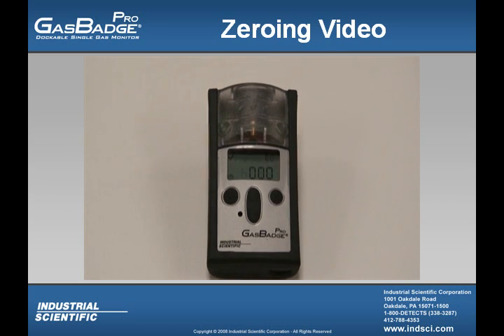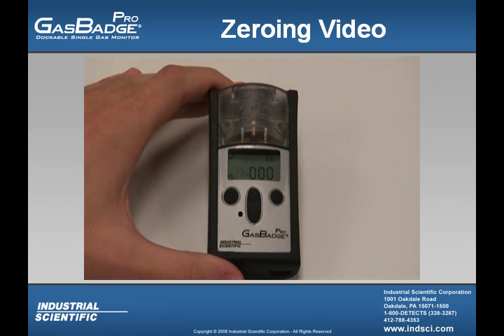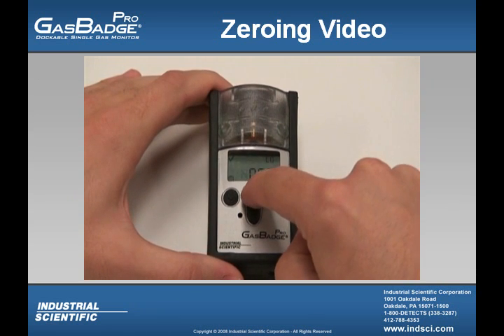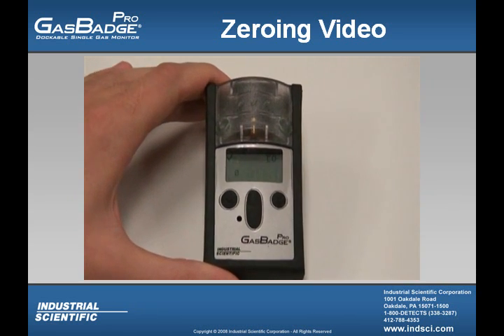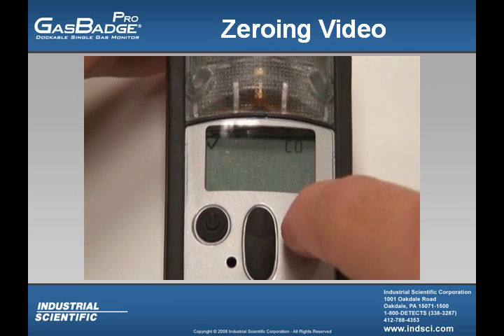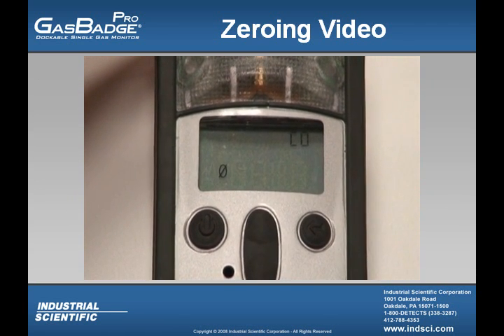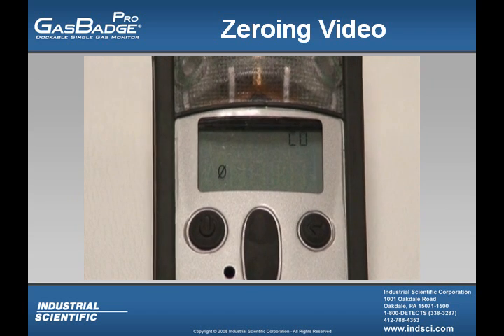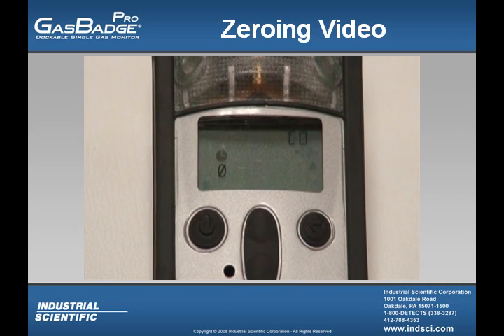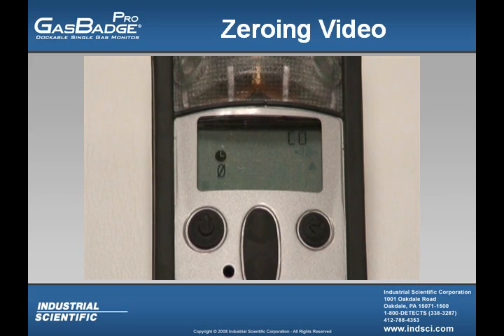Let's take a look at how to zero the GasBadge Pro. Most importantly, you want to make sure to only zero the instrument in a fresh air environment. To zero the instrument, you're going to want to press the up button once. You should see a 0 with a slash through it blinking, and you're going to press the enter button. From there, you're going to see the clock symbol flashing, and this is just letting you know that the instrument is in a zeroing mode.